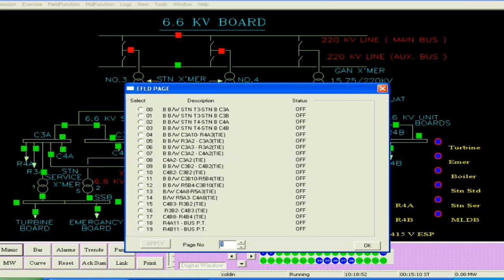Then we go to page number 1, index number 00 to 04, and then index number 17 on page number 1. Then we go to page number 15. Index number 17 is a tie, that is C4B to R4B. From C4B, that is the station, the supply will be extended to the R4 unit board. R4 is the unit board.